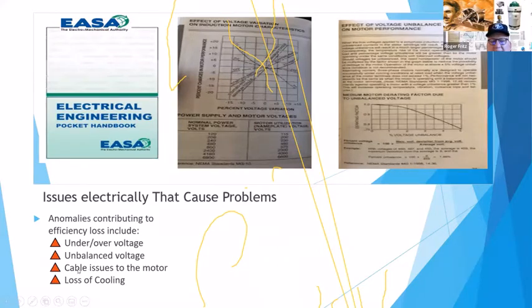The other area that happens a lot in submersible applications is cabling. And I briefly discussed a little bit about the output cabling lengths. It's important that we also look at the noise factor that comes about because of that PWM. So that's why a lot of discussions going on today are about having isolated, shielded cables that come out of VFDs, especially if you have major lengths, meaning that it basically has a shield that goes around the outer plastic that goes also in the cable, so that the motor leads, or the output leads, don't start cross-talking.